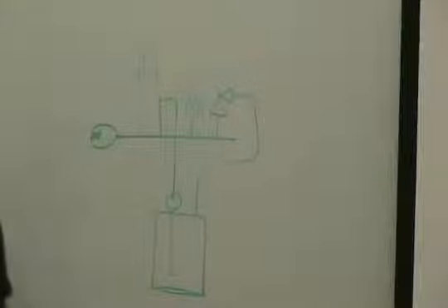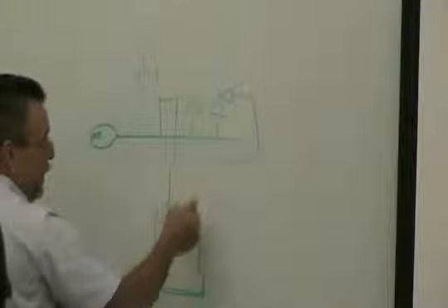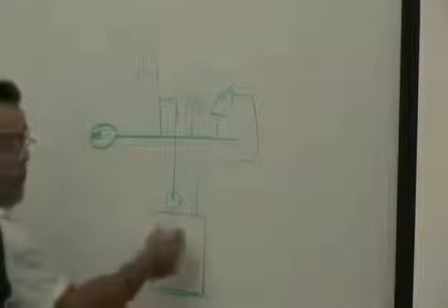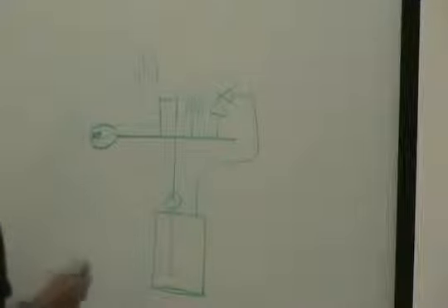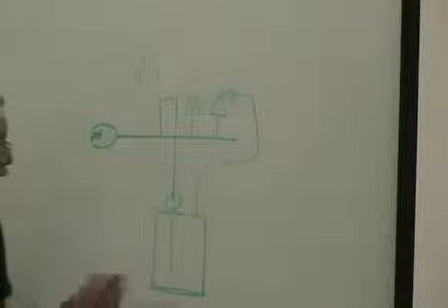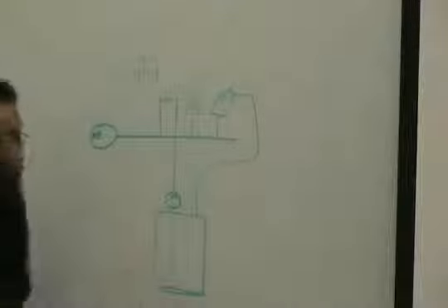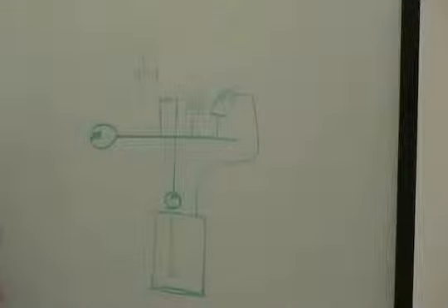And then you would have a glycol tank and a feed pump that operates on a pressure switch right here. So whenever you lose pressure, whenever you relieve water, the glycol is pre-mixed water. Oh, okay. So it's water and glycol, pre-mixed in whatever solution that you want, 20%. So it's metered into your water system? Yeah, this pump is metering it in based on the pressure. Okay, so it's just not all mixed together. Right. Okay, I got you. That's how most systems work. But in theory, once you get your glycol in there, it's pretty good.